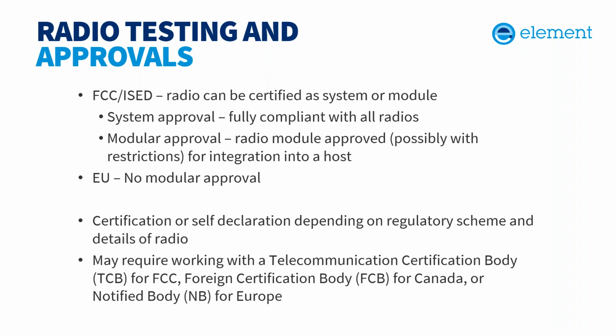The system approval path can be the right path if you can't use modules due to design limitations. Again, with a pacemaker, they're so cramped for space that they can't rely on another manufacturer to make the radio. If you're doing system approval, you can basically do whatever you want within the FCC or EU rules. You're not limited by the module manufacturer. You have control over the design. System approval also tends to be cheaper on a per unit basis, but there are some economic considerations that we won't go into today. It might be cheaper per unit, but it depends on how many units you're doing and so on. Another thing with system approval is that not all regions accept modular approval, so you might need to certify as a system for certain markets.